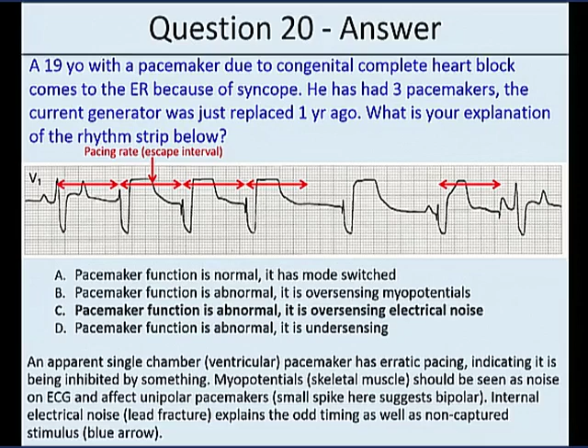Early pacemakers were all unipolar because it's just easier to manufacture a lead that's only one electrode. Pacing thresholds are a tiny bit less with a unipolar. It's just a lot simpler device, so batteries would last a little longer. But you did have this problem with sensing skeletal muscle voltage, which is about the same size of a signal that the ventricular muscle would have, and you end up inhibiting with that. Bipolar pacing, small spike on the ECG, it senses over a very small range. The two electrodes are right in the ventricle there, so it doesn't see myopotential. So myopotential oversensing would be a very poor cause, low likelihood of causing this problem here. So this is lead fracture. And I think with that, I am done.